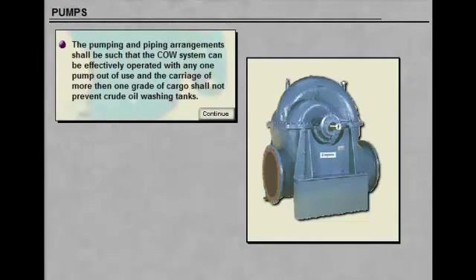The pumping and piping arrangements must be such that the crude oil washing system can be effectively operated with any one pump out of use and the carriage of more than one grade of cargo shall not prevent crude oil washing of tanks.